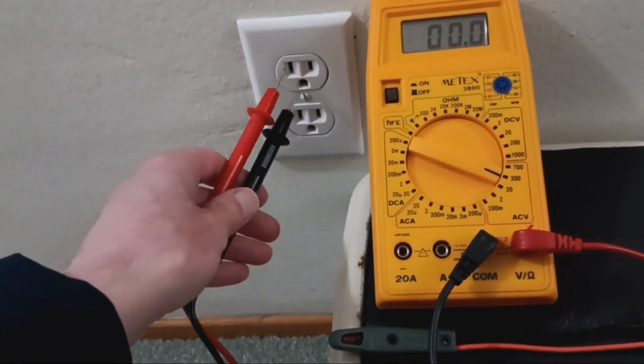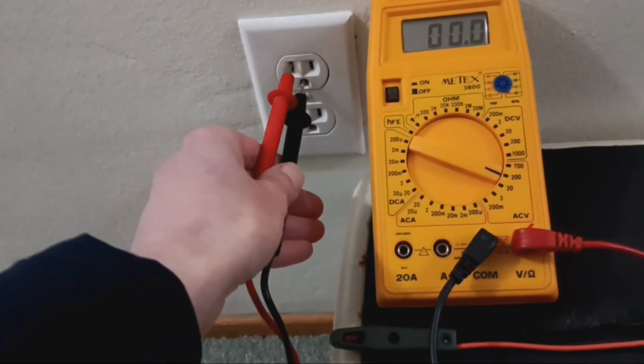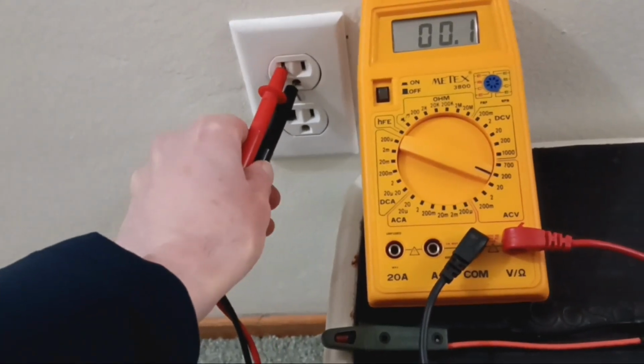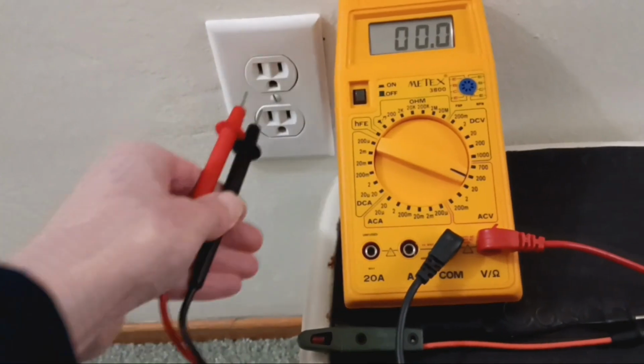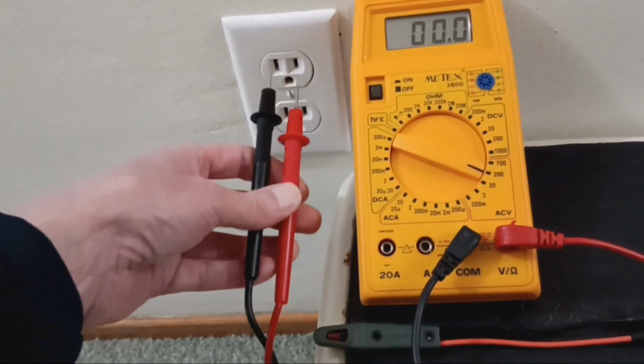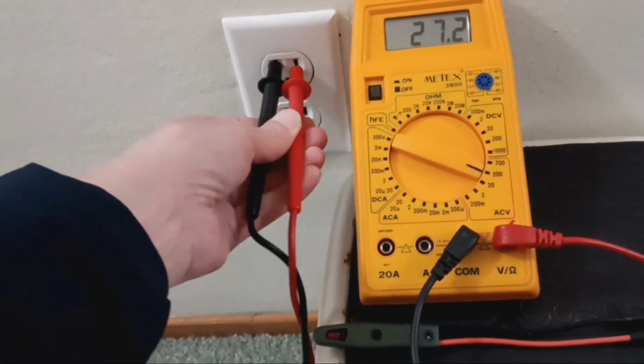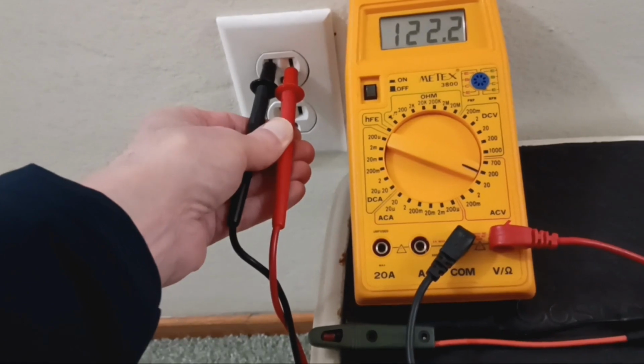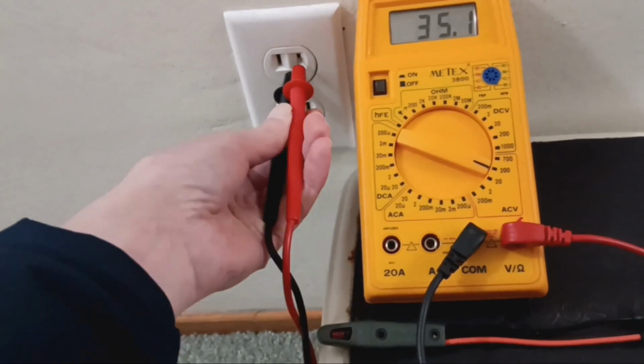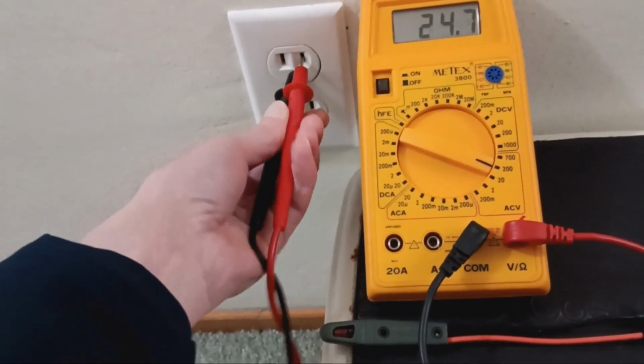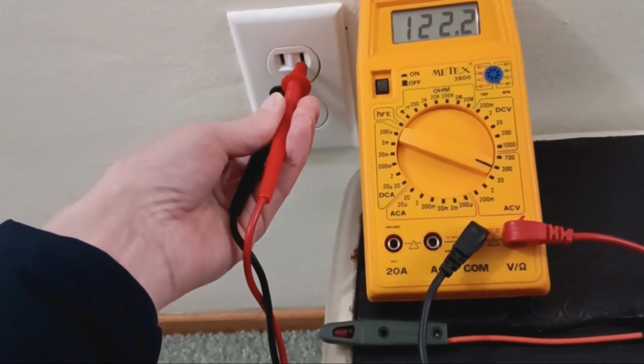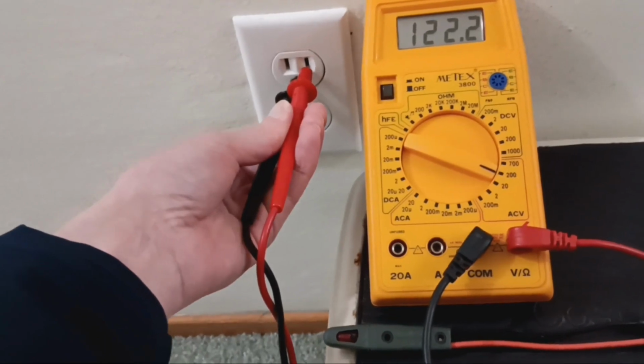I'm going to read the voltage from the ground to the neutral first, and that's reading about 0. Now I'm going to read the voltage from the hot to the neutral. That's reading 122.2. Now I'm going to read from the ground to the hot. That's reading 122.2. So those readings indicate that the outlet is wired correctly.